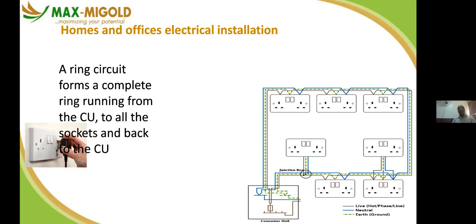In electrical installation, we have the ring circuit installation and the radial. A ring forms a complete ring running from the consumer unit, the CU, to all the sockets and back to the consumer unit. What that means is that the ring carries the live wire with the neutral to all the sockets in a ring form. They are looped together. So it's not that advisable in modern day installation.